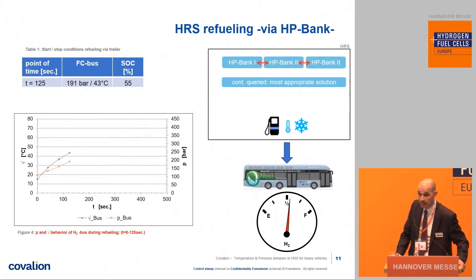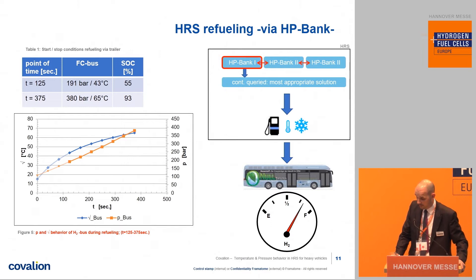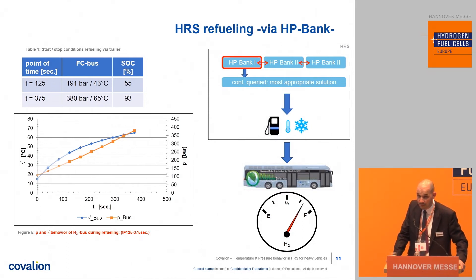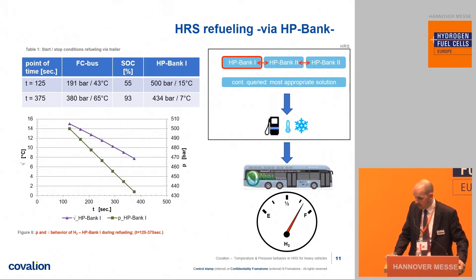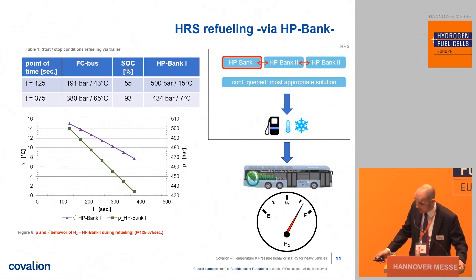We now switch to HP bank one, as this is the next most efficient way. The software indicates we need HP bank number one, we open the valves, and the refueling continues. We reach a stop criterion again — temperature, pressure, or mass flow. After 375 seconds we reached 380 bar at 65 degrees, and we have not yet reached the 95% SOC target, but we are almost there at 93%. You can see clearly the temperature behavior in the bus during refueling. The behavior in pressure bank one is inverse to the pressure behavior in the fuel cell bus — we see a temperature drop from 15 degrees down to 7 degrees, and from 500 bar down to 434 bar.